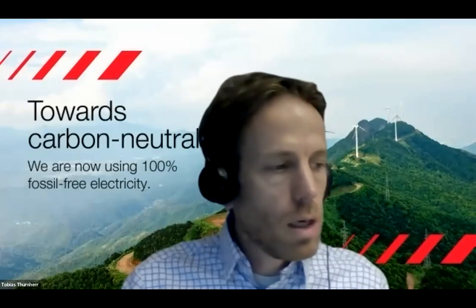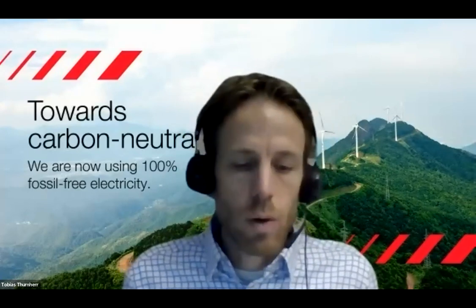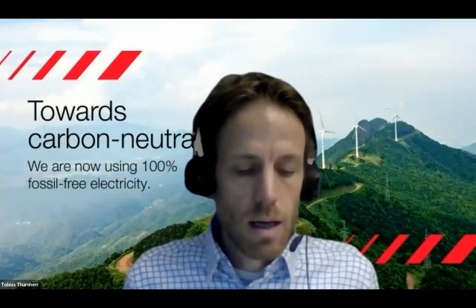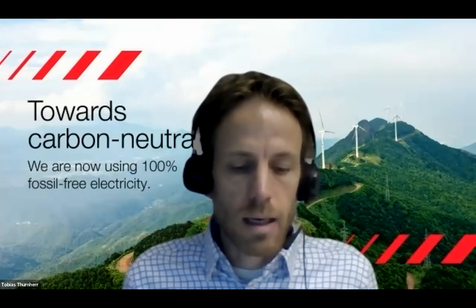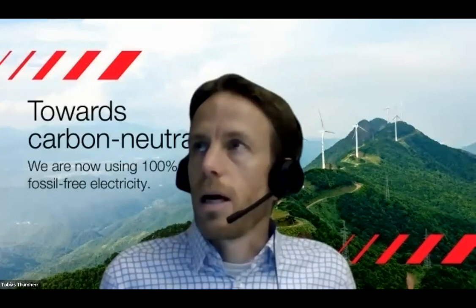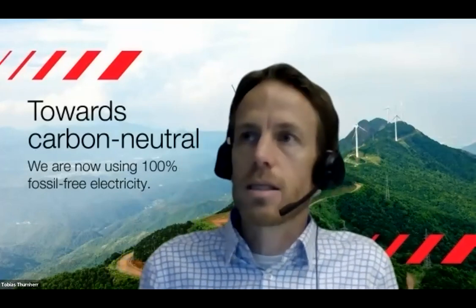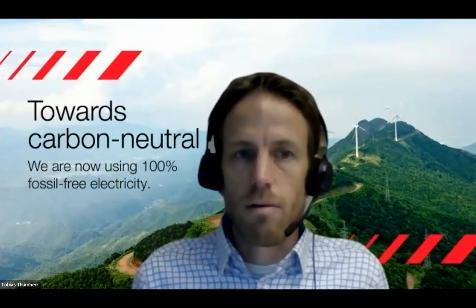Okay. So we've got Colin, there's two comments on here. Do you need to have a communications link between multiple SFCs to ensure accurate load sharing along a track section? The SFC slope load response would automatically compensate for this. We don't necessarily need it. No, there are different ways to control the SFC. If it's operated together with a transformer, I think I've shown this phase measurement unit, then this setup allows to prevent power to flow through the catenary that should flow through the utility grid. It's not a direct communication link giving reference values, so the timing requirements are not that strict. It's just the transmission of this phase angle and the timestamp.